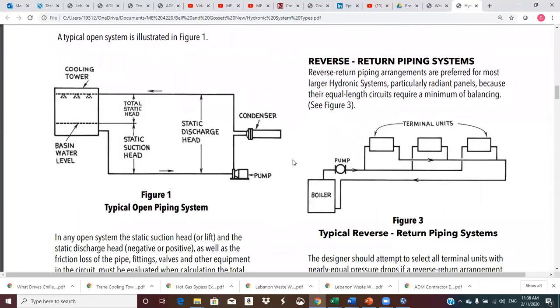And probably the cooling tower, for an open type system, is a good example. So this would be the basin on the tower. So this is flooded with water, and this would be the surface, the top surface of that water. And so when the pump operates, it draws water from that basin, and this is the elevation level of reference, which is the surface, and the water flows into the pump. Say it gets pumped through a heat exchanger or gets pumped wherever, and then comes back out, picks up energy, comes to the back top of the cooling tower where it is sprayed out. And so we have a break. So there's no pipe from here to here. The water is falling down. So this is considered an open system. And this elevation from where the water comes out of the piping system up here to this free surface is called a static head.